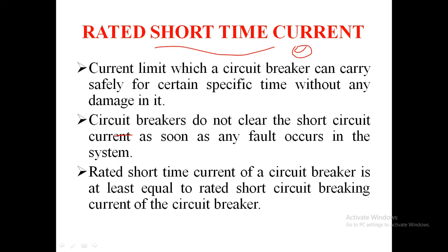Temperature rise depends on the conductivity of the material, represented by sigma. While designing, a high conductivity material must be chosen; if the conductivity is low, then the cross section of the conductor is increased. This is how to rate the short time current. It should be at least equal to the rated short circuit breaking current of the circuit breaker.